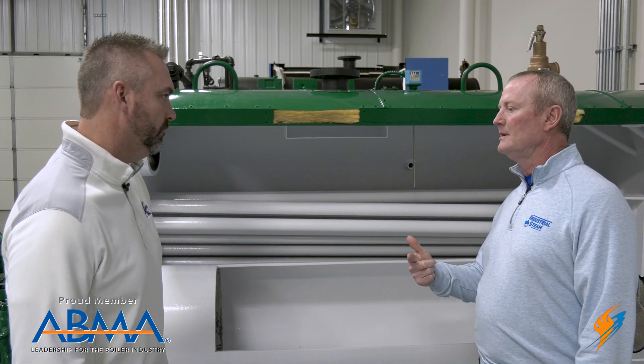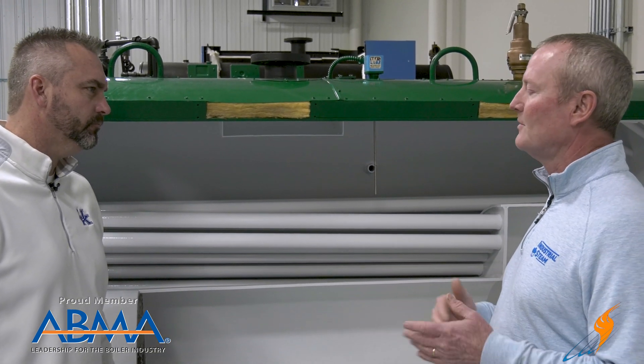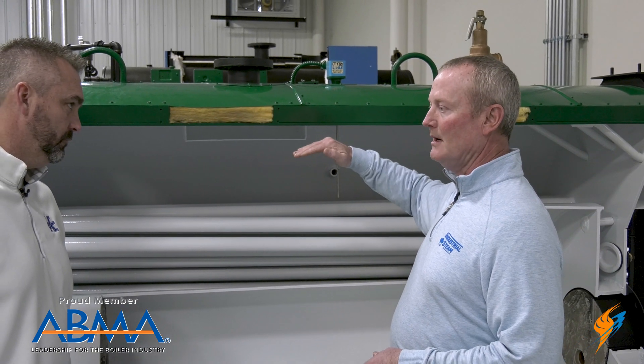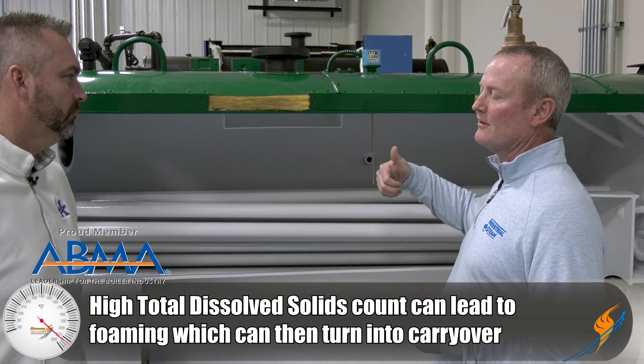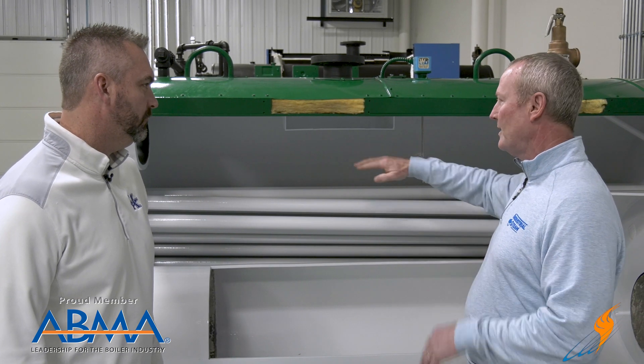The first and most common is caused by hard water where they're not treating the water properly. They've got high magnesium, calcium, whatever it is in their water. Their water softeners aren't working, they're not treating things properly. The feed system is dumping it straight into the boiler. The TDS — total dissolved solids — gets up really high. Typically you run 3,500 TDS, but if it gets up in that 6,000–7,000 range, you're going to start carrying over. That's where those steam molecules start collecting that hardness — instead of separating, they'll collect. Those go entrained into the steam, out into the system. It can get to a point where it's no longer steam — you start actually sucking the water and just shoving water out into the header.